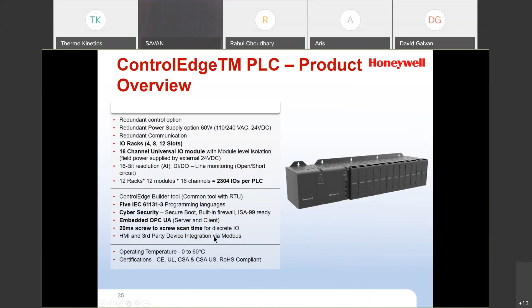So the two forms and fashion, again: if you're going to use a redundant CPM, central processor module, then you would utilize this rack. And then this, instead of being a CPM, now becomes an EPM, extension processor module. So basically you connect your uplinks and downlinks, either star or ring, to your I/O rack, and this will be your remote I/O rack out in the field. This box will be in your ICR, ECCR, or server room, wherever you need it to be, handling that function as the CPM.